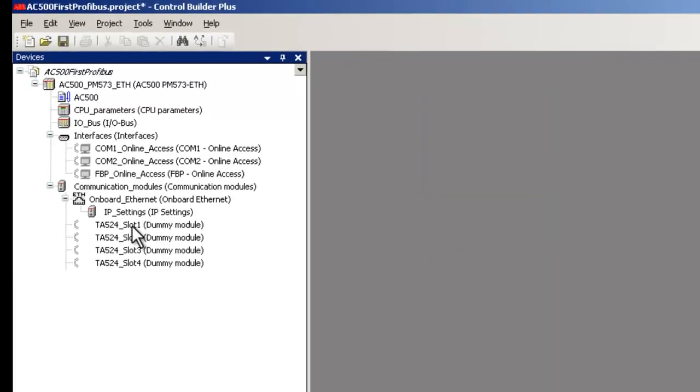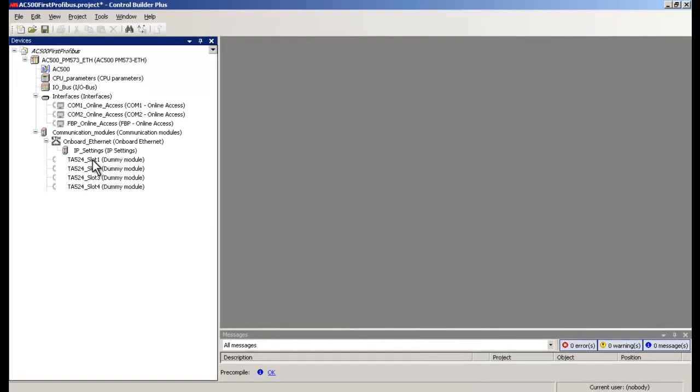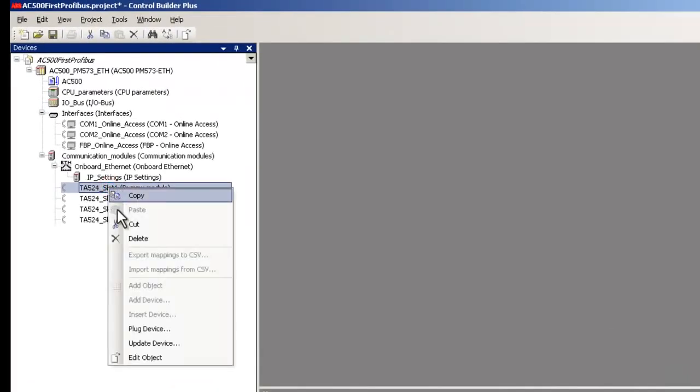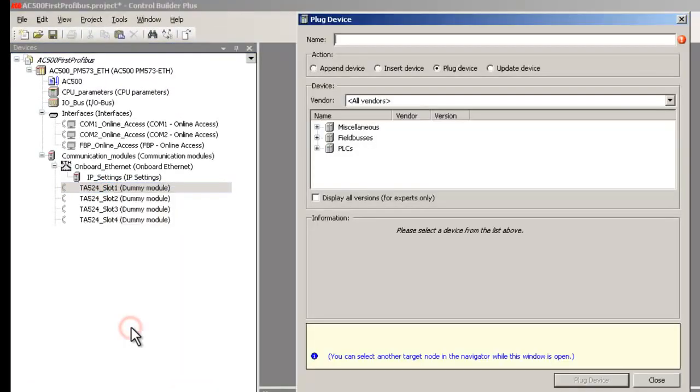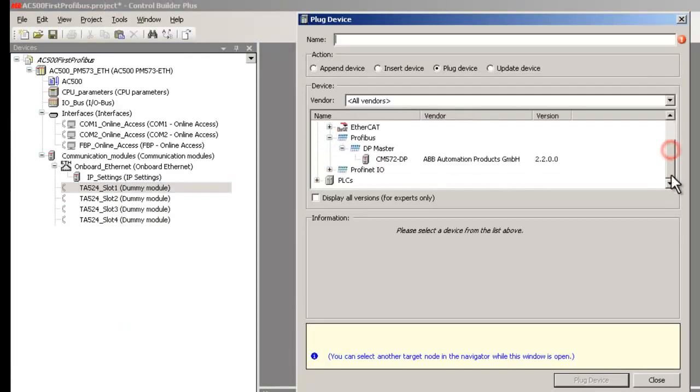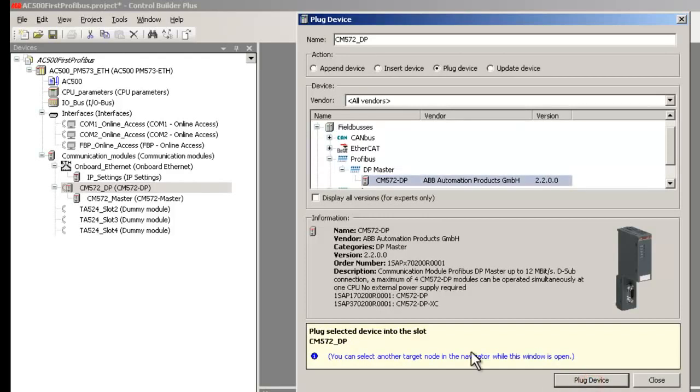In order to change the default configuration, right-click on the first slot and choose the option Plug Device. A dialog box with the module list appears. Select the option Field Buses, then PROFIBUS, and CM572DP from the branch DP Master. Click the button Plug Device to validate your choice. As a result, a PROFIBUS master system is created.